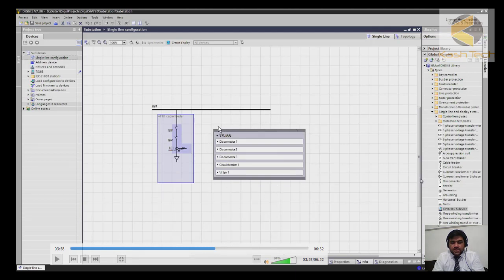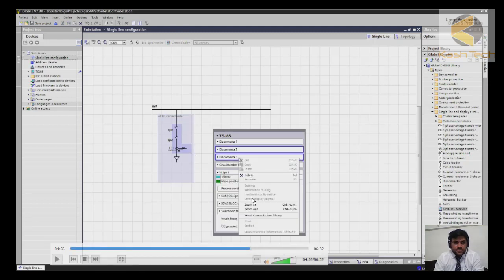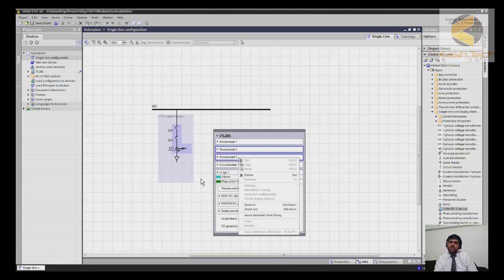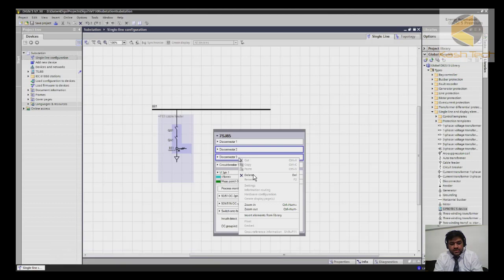Once the configuration is ready, you will see the element 7SJ85, which is an overcurrent relay — SIPROTEC 5. You can see disconnector one, two, and three — up to three disconnectors can be connected to this relay, along with a circuit breaker. The voltage/current element is three-phase. In our application we have one disconnector, one breaker, and one CT. Since we only have a single bus bar, we need only one disconnector, so we select disconnectors two and three, right-click, and delete them.